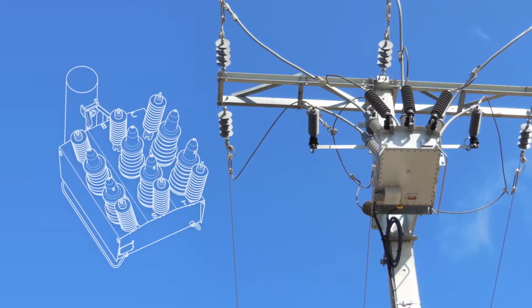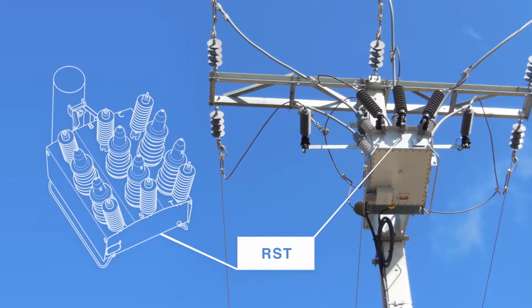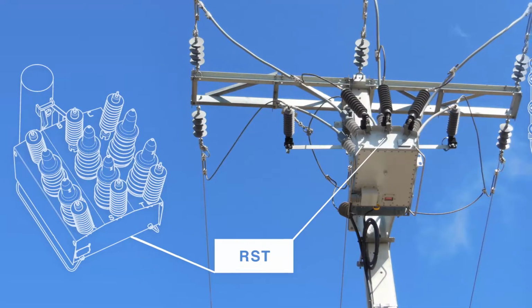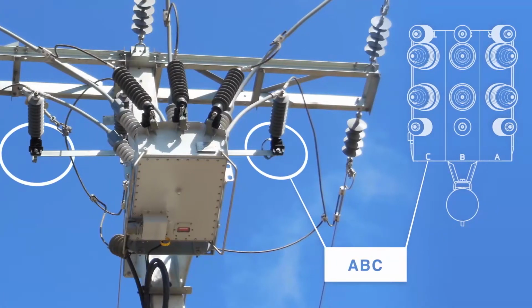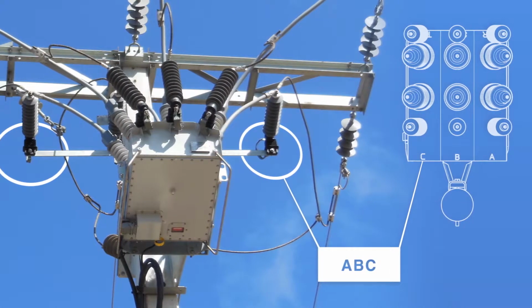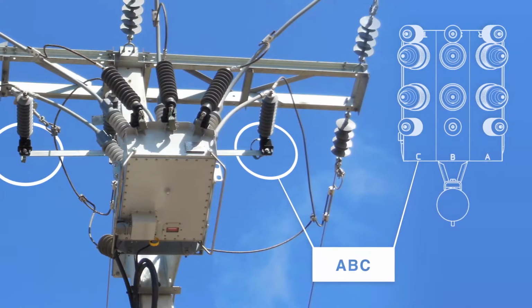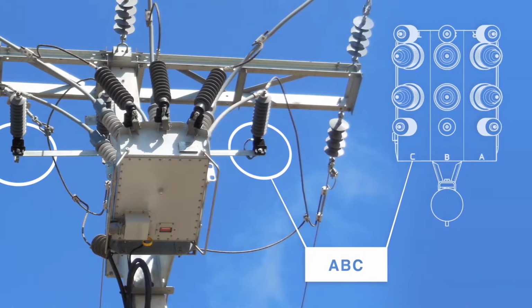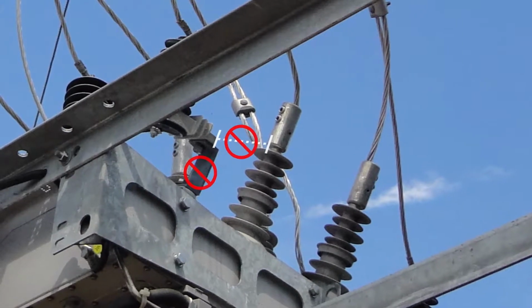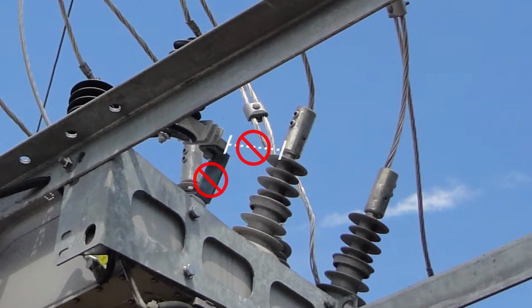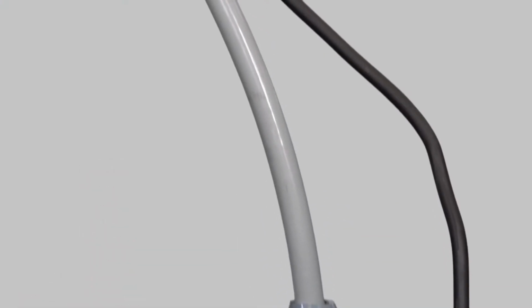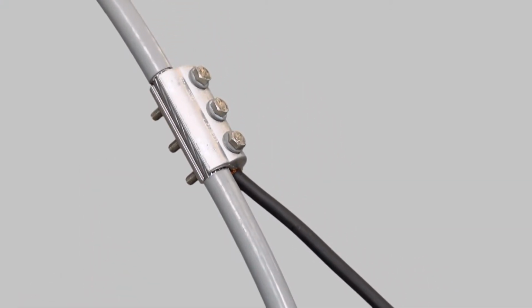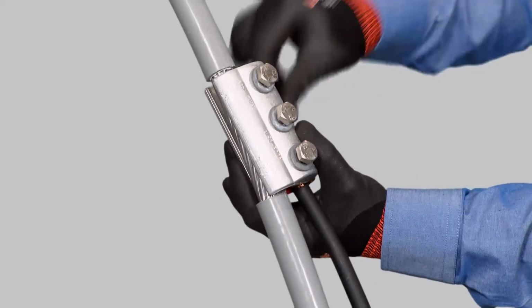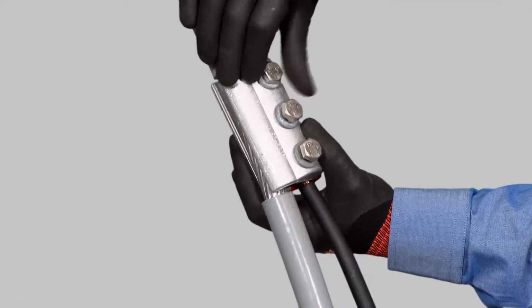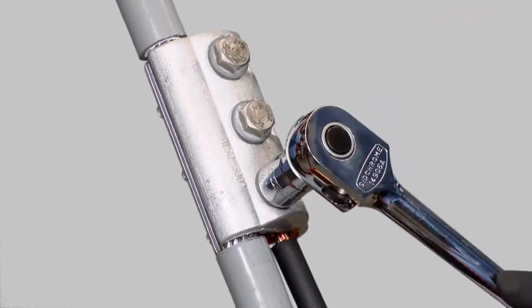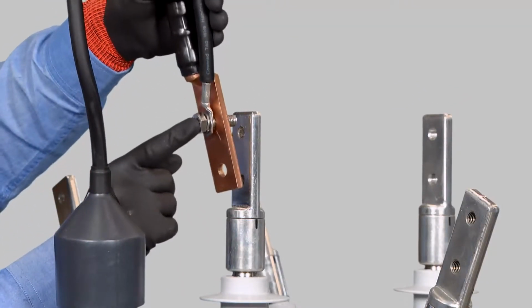Surge arresters with standoff brackets can be mounted directly onto the RST side of the tank. On the ABC side, they'll need to be mounted onto a separate crossarm. An earth conductor should be run from the surge arresters to the main earth. Incorrectly installed standoff brackets can reduce phase to ground clearances. The surge arresters should be connected close to the recloser terminals. Connect to the cable tail with a parallel groove clamp when using tunnel connectors. Use a crimp lug under the bolt when using palm connectors.